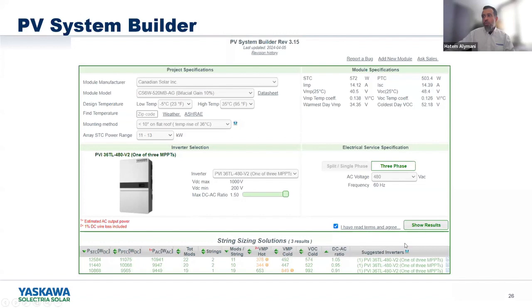So as soon as you show results, the tool is going to provide you with options. As you see here, the tool is only going to provide options for one MPPT, and then you can do the same on the other MPPT or use different recommendations on the other MPPTs. So here, let's assume that we have one string of 19, 2 of 10, and 2 of 11. So you can basically go and say, oh, MPPT 1, I'm going to put 2 of 11, MPPT 2, I'm going to put 2 of 10, and then MPPT 3, I'm going to put 1 of 19.